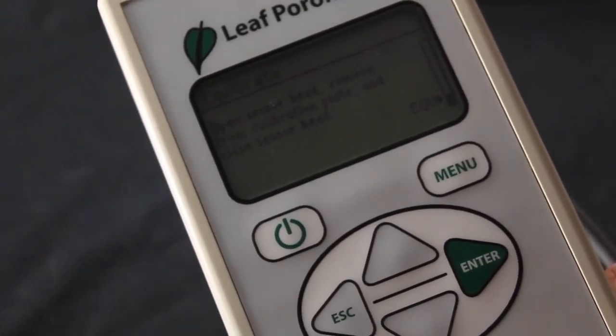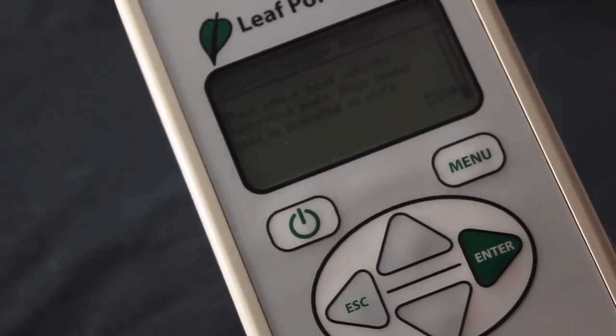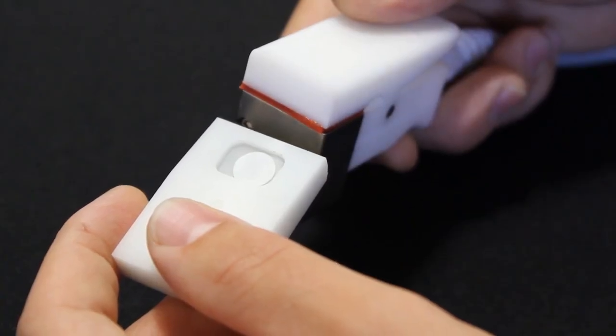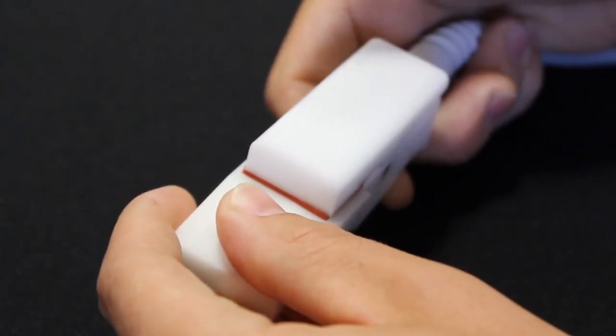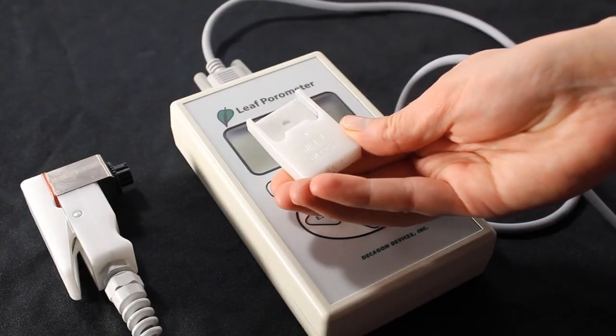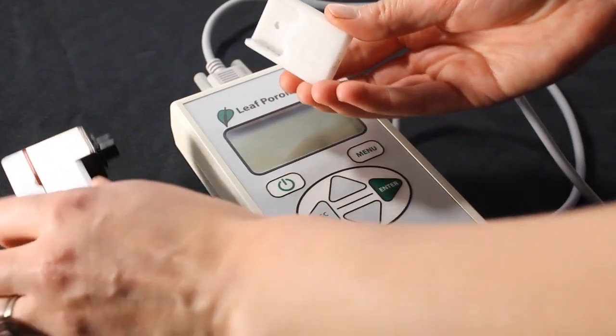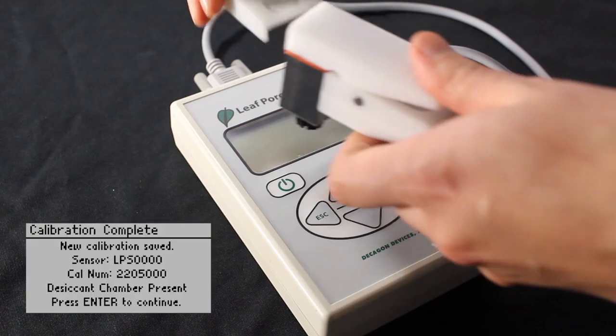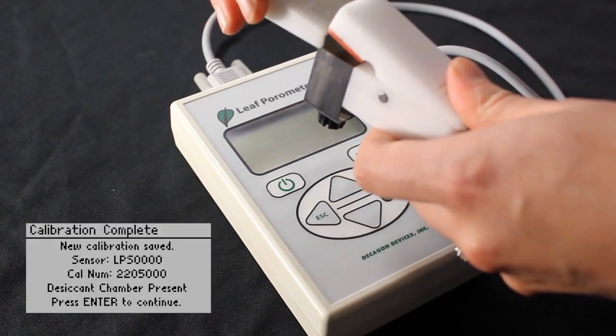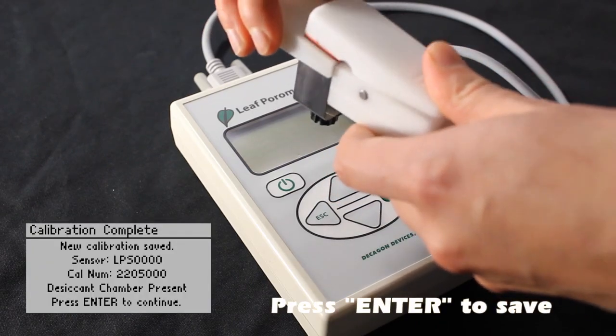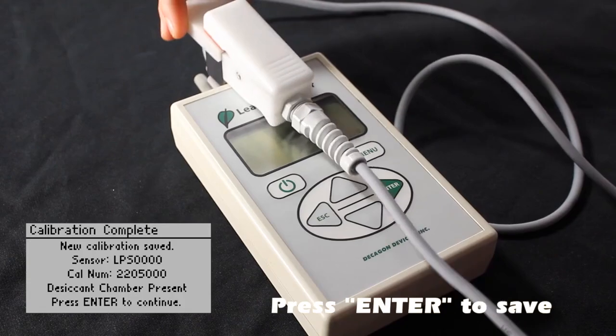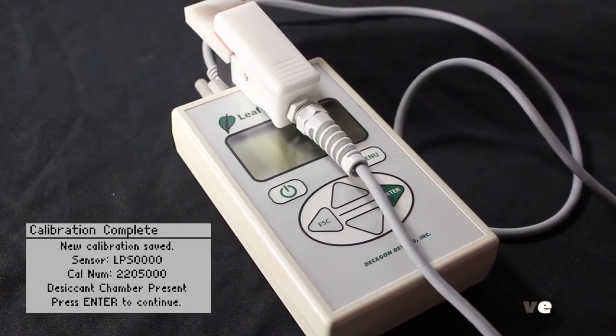Once the two sensors equilibrate, you will be prompted to attach the sensor head to the calibration plate and take a second equilibration measurement. Again, do this part quickly to prevent the chamber from reading the ambient air. This process will be repeated until 3 consecutive measurements are all within 7.5% of each other. This usually will occur after 3 to 5 readings. Once the calibration is complete, press Enter to save it into the handheld unit, and the following screen is displayed.